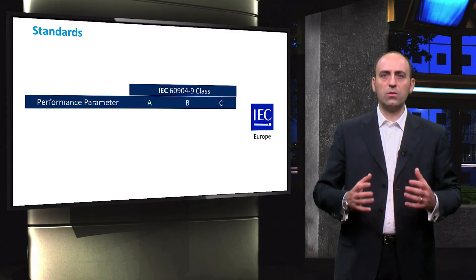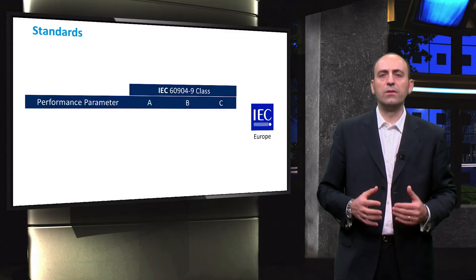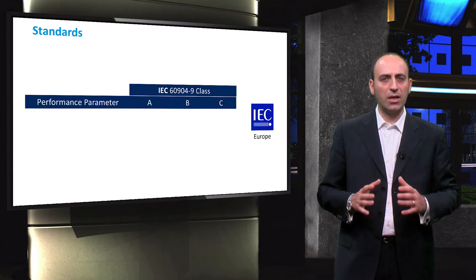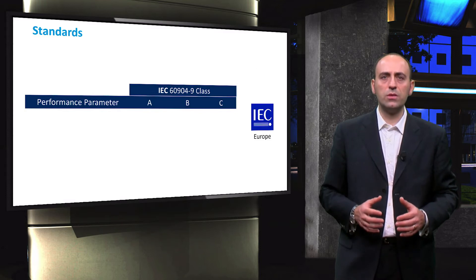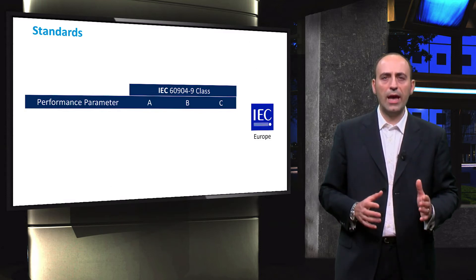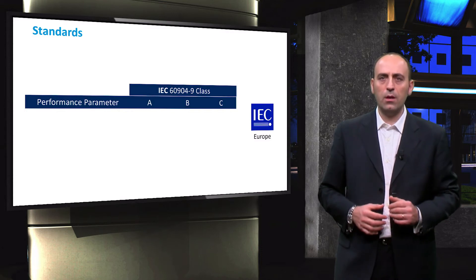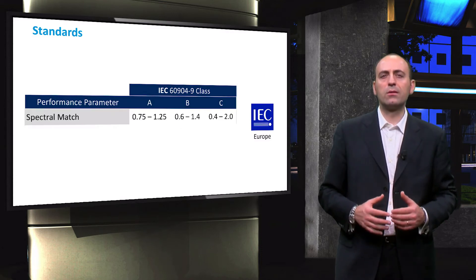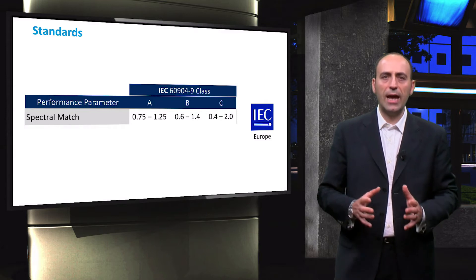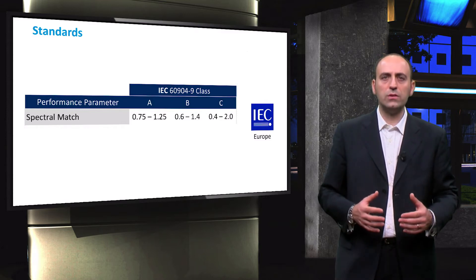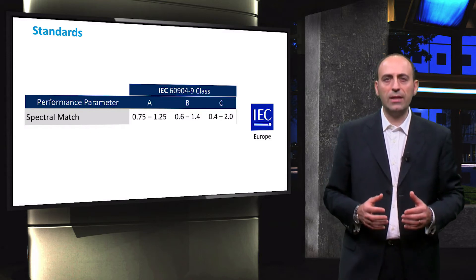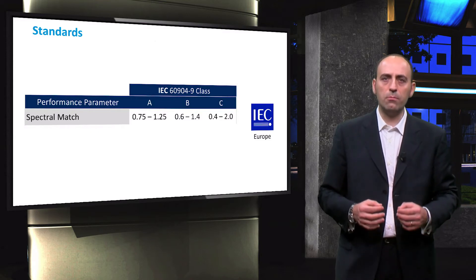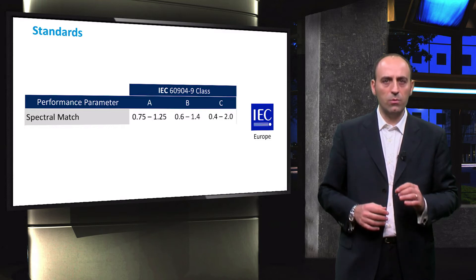The goal of a solar simulator is to replicate the natural sunlight spectrum as accurately as possible. For this reason, the European International Standard uses three performance parameters and each can score A, B or C. The first one deals with the spectral match between the light source and the AM1.5G. The higher the score, the narrower the error margin allowed, and in the following slides we will define in more detail each category with some examples.